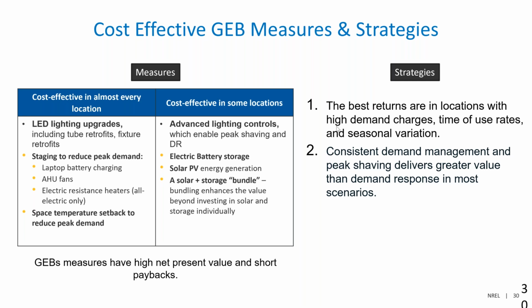On strategies, the best returns are in locations with very high demand charges that have time of use rates and seasonal variation. Secondly—and I think this was a key outcome of this project—consistent or continuous demand management really delivered greater value than just responding to utility-driven peak demand or demand response events. I take that to heart as a building scientist at NREL: we really need to focus on continually managing our demand and understanding where those opportunities are.